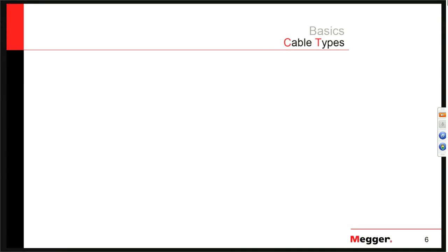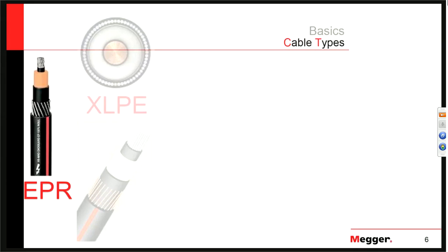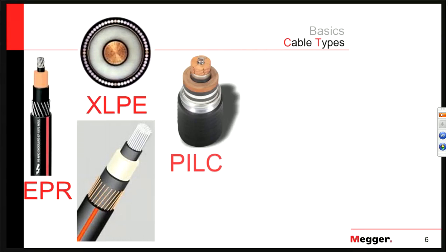What kind of cables are we going to talk about? Most commonly, we'll see EPR, XLPE, or PILC type cables. EPR and XLPE are often lumped together as extruded cables or solid dielectric cables because the bulk insulation material is solid — EPR feels a bit like a pencil eraser, XLPE feels more plastic-y. PILC cable is treated differently because the insulation is paper wrapped around the center conductor and filled with oil.